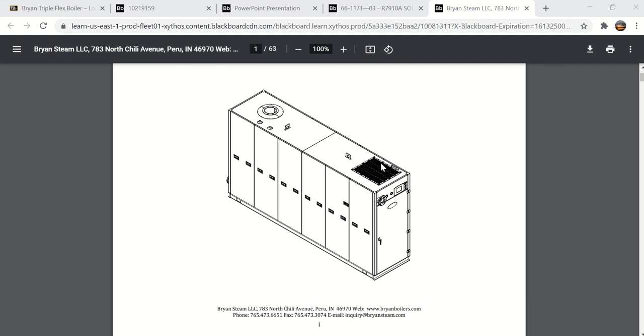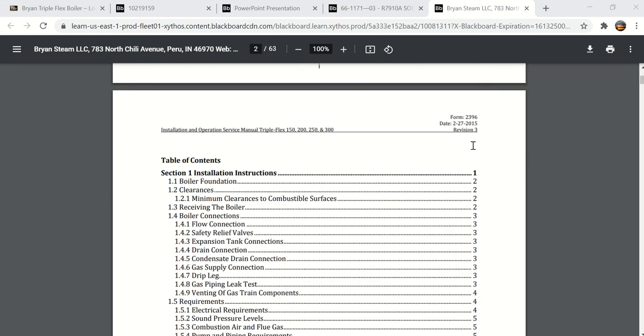Air pulls in right here. The air goes all the way underneath the cabinet on top, back here to where the combustion blower picks up the air. It pushes it through a heat exchanger that's right here. Flue gases are going the opposite way through that air-to-air heat exchanger. Then the air comes all the way back up to the front through a piece of pipe and goes into the burner there. The window right here, you can see the actual burner, and then the water tubes, and then finally the flue gases come through the heat exchanger and out the top there.